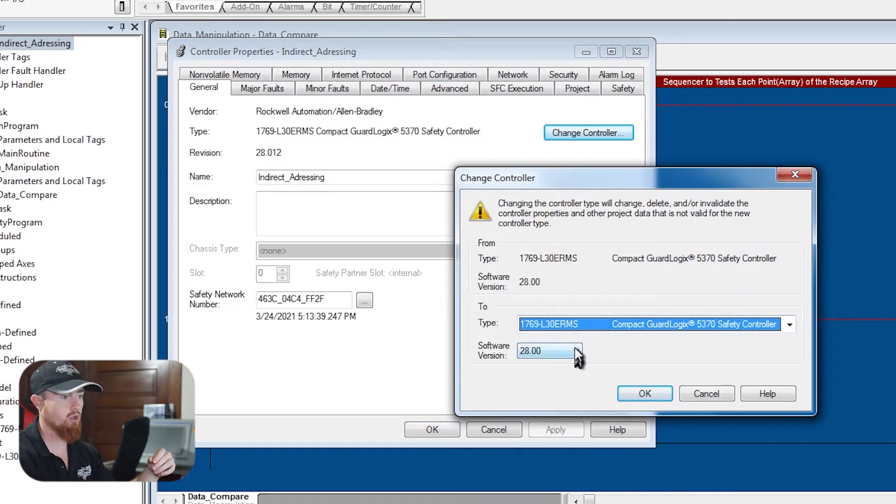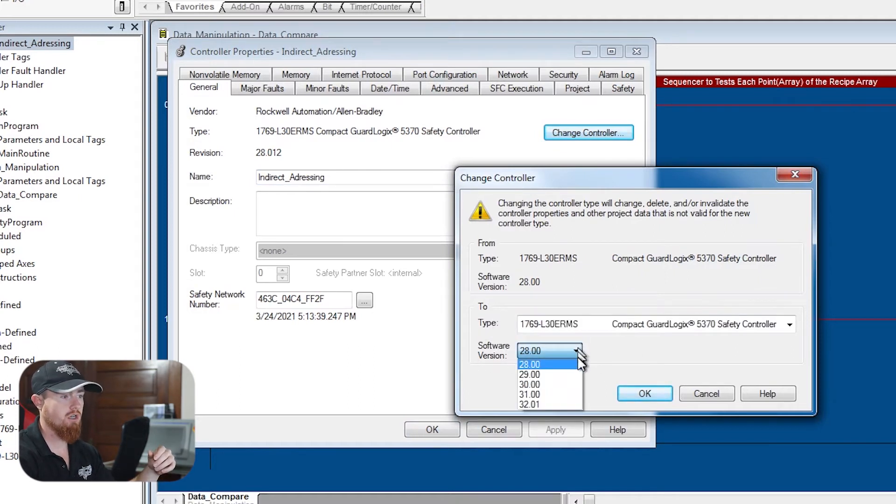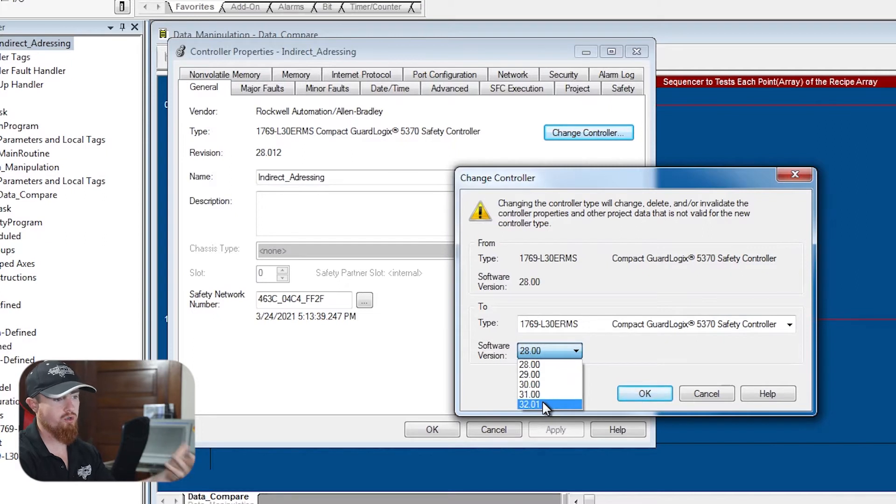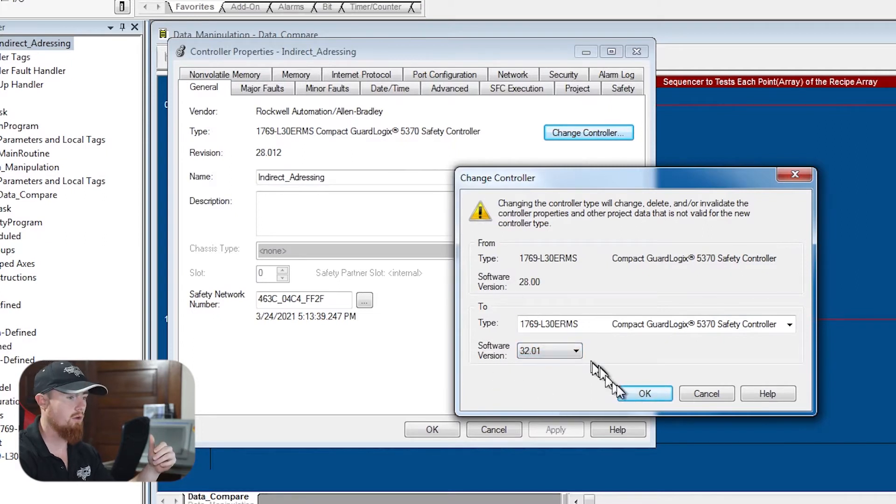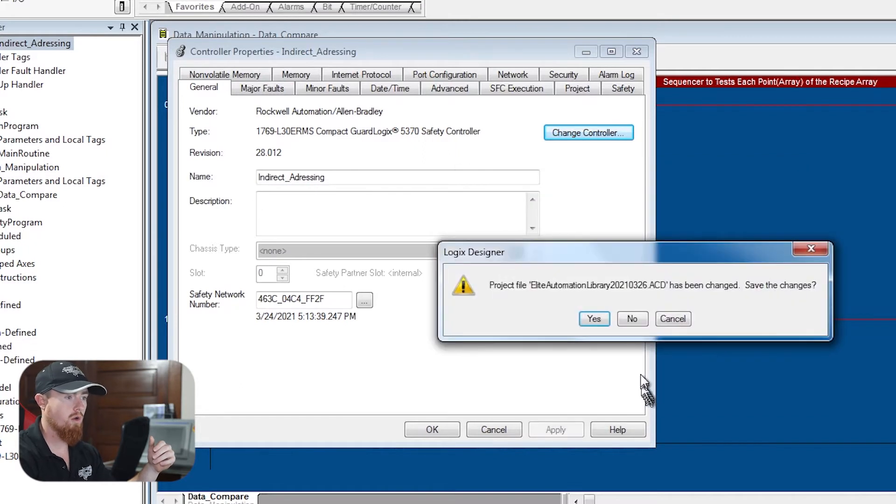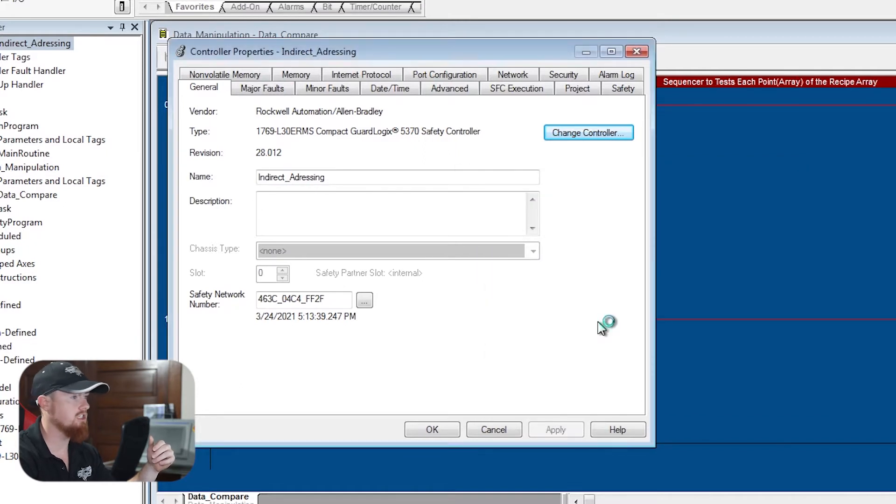So you click change controller and as you can see right here, software version. So we're going to change the software version to the current version that we just seen in that little pop-up dialogue box, which is version 32. We're going to okay it. It's going to ask, do we want to save the changes? We'll just say yeah.